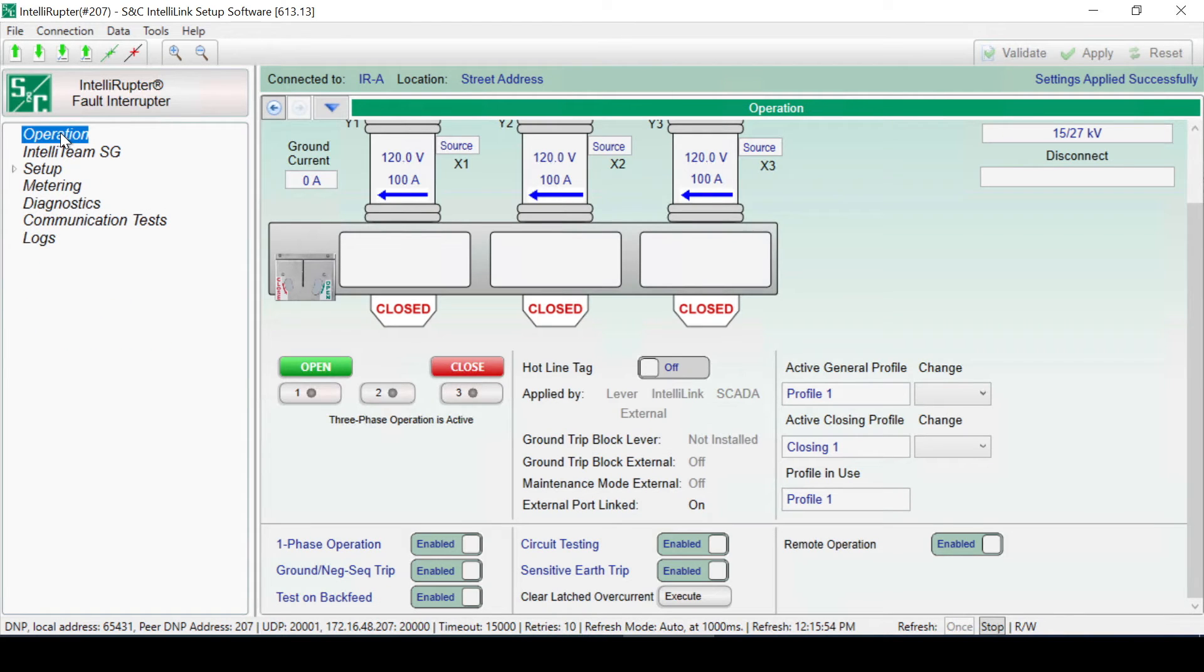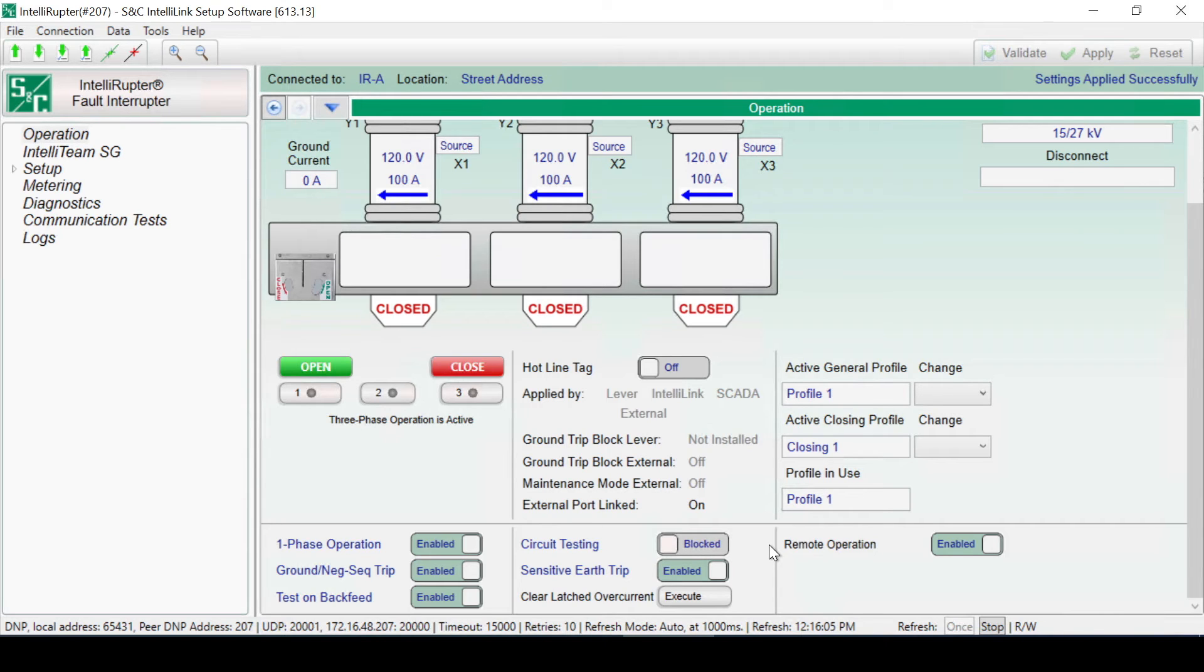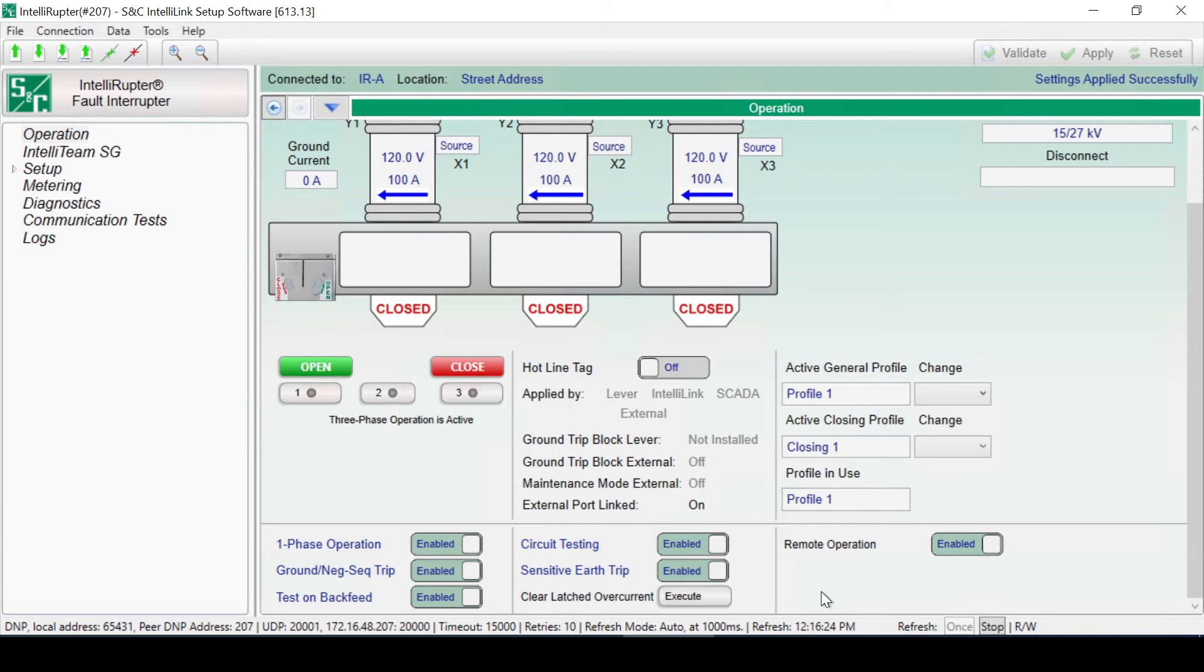Circuit testing can be enabled or disabled using this slide control. Many utilities refer to blocking circuit testing as one-shot mode. When circuit testing is disabled and a fault occurs, the switch will trip directly to lockout. Only when circuit testing is enabled will the switch perform a test sequence after a fault. This control only applies to the general profiles because they are the only profiles with circuit testing. Both closing profiles and the hotline tag profile are always one-shot to lockout.